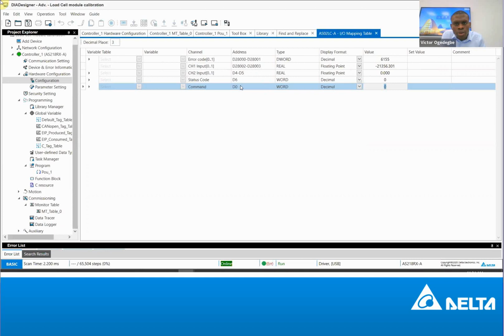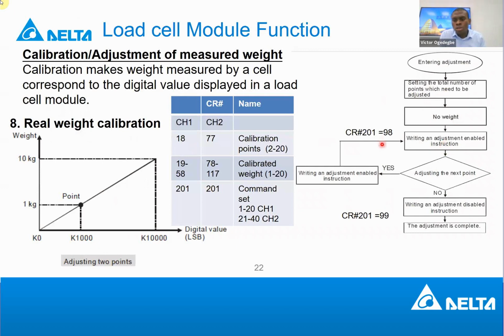Status code, command. So what I'm trying to say is that when you write it here, like I'm online now, for example, if you write a command on this D0, without using the TO instruction, it goes to the register you are calibrating. So you can do it from the monitor table. But with this, you are a little bit limited because you don't have access to a lot of parameters. With the control register, it was a little bit more flexible, which I showed you here.